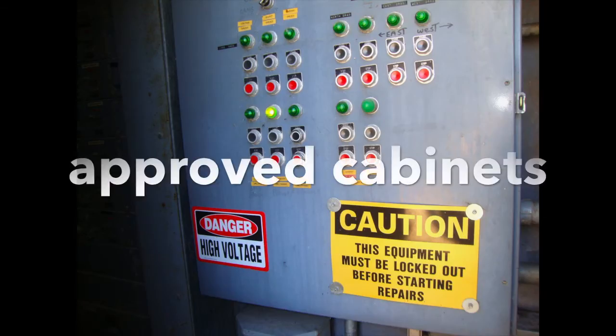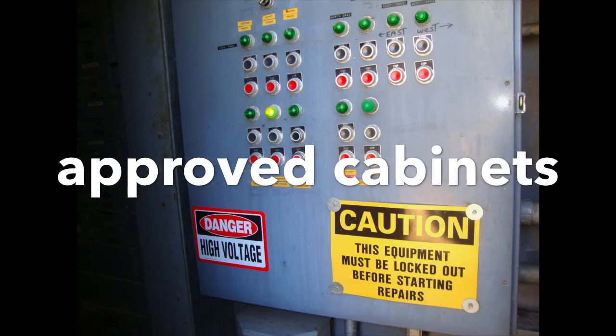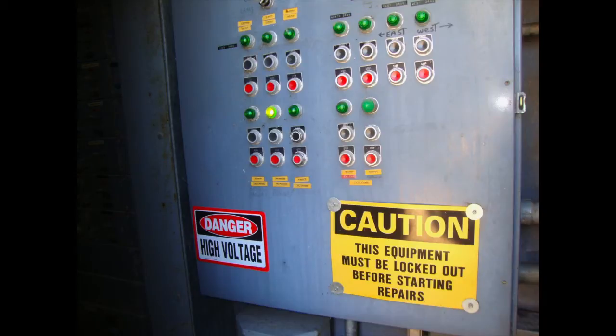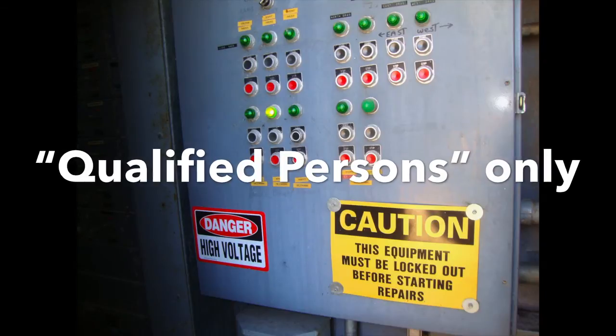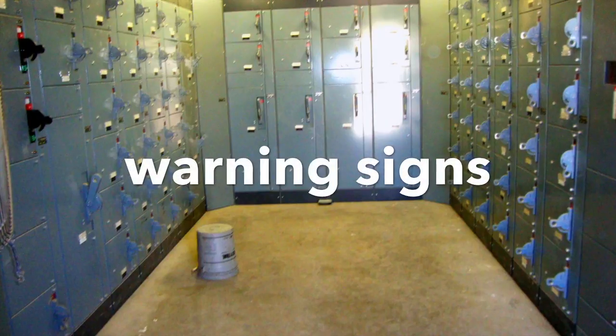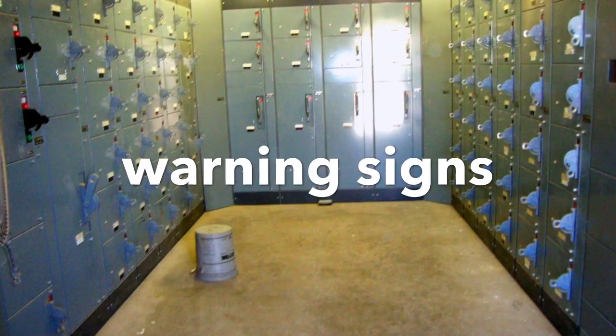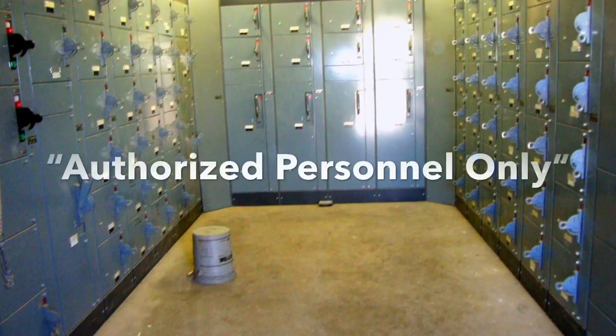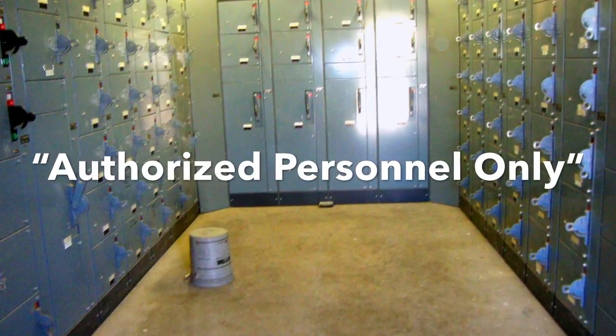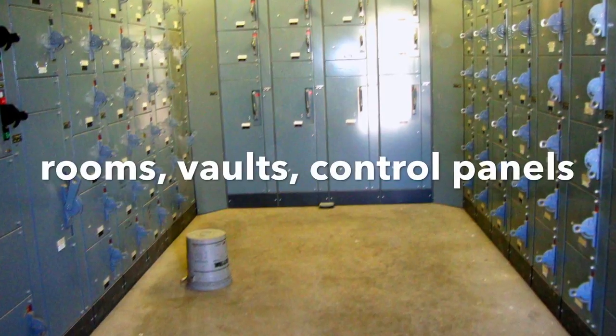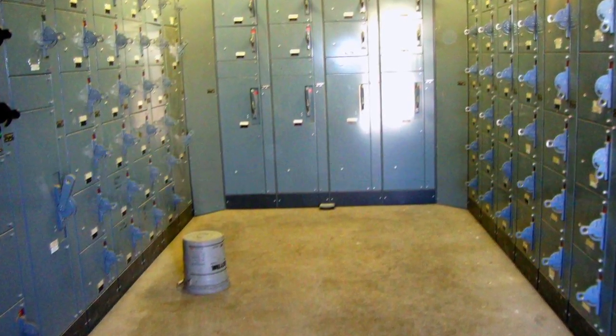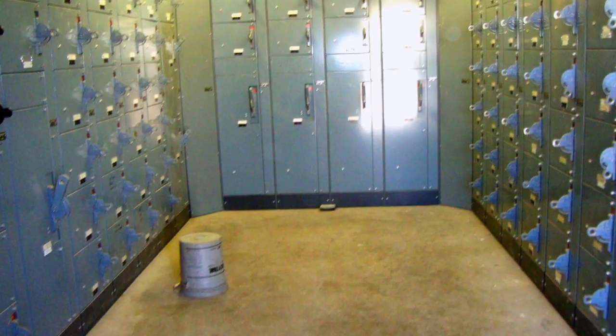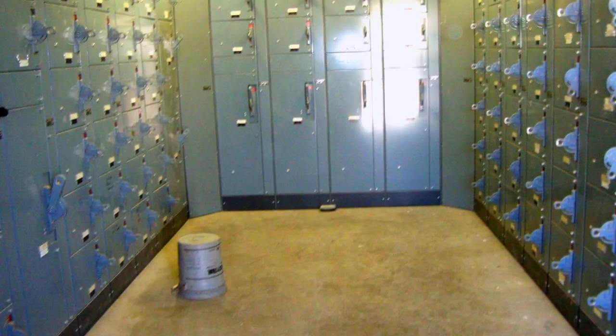If the equipment has live parts of 50 volts or more, it will be guarded by approved cabinets or other approved enclosures. The equipment may also be set up in other locations that are only accessible by qualified persons. Entrances to rooms and other guarded locations will be marked with warning signs forbidding unqualified persons to enter. For instance, it might say authorized personnel only. This would include the following: rooms, or vaults, or control panels, and any room or enclosure that gives direct access to live parts by unqualified persons.